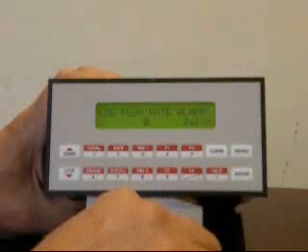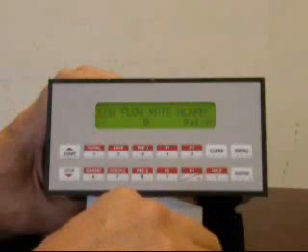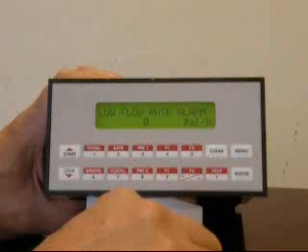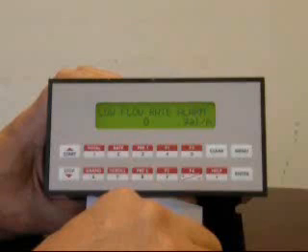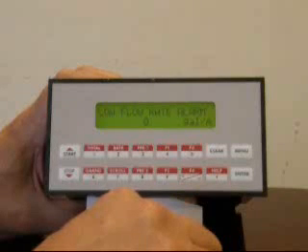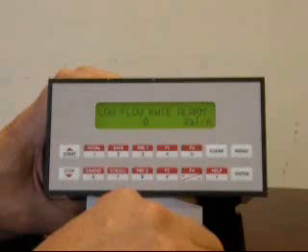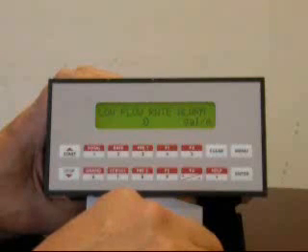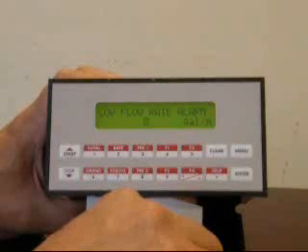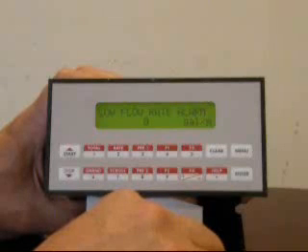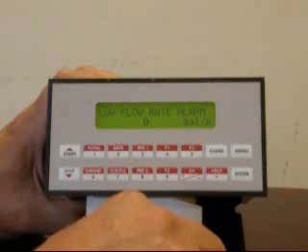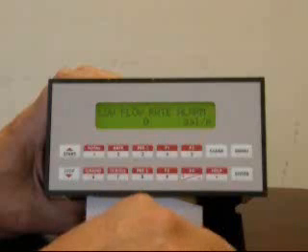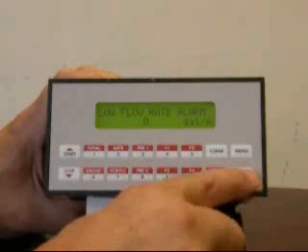There are warning alarms that can be signaled to the operator when his flow meter is being used out of range. In the case of a 2 inch meter of the turbine type, a range of perhaps 10 to 220 gallons a minute would be considered satisfactory. We're going to leave a setting of zero in this case since the application is assumed to have periods of no flow where we're not trying to create a nuisance alarm warning to the operator.